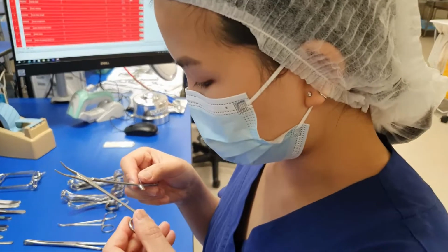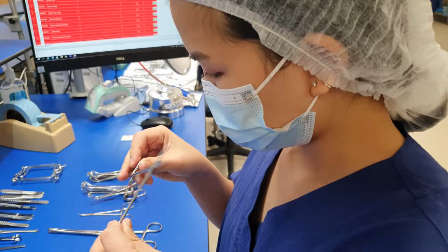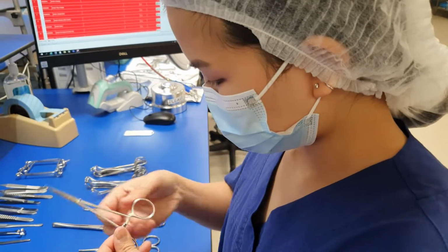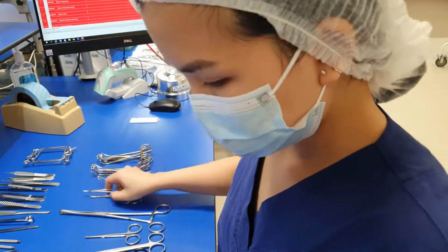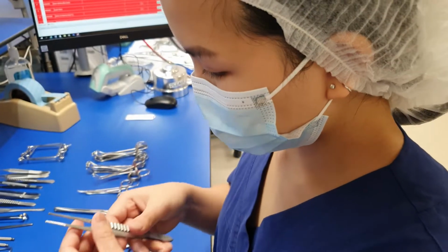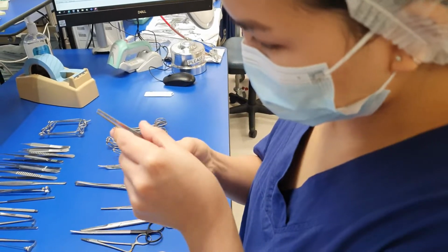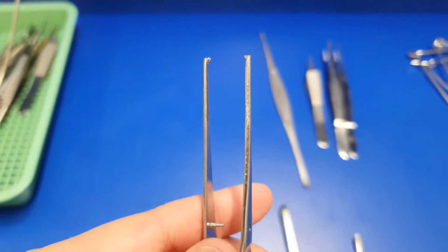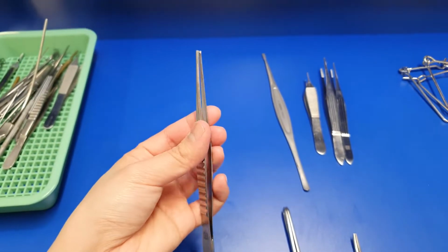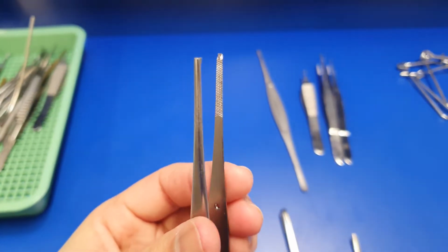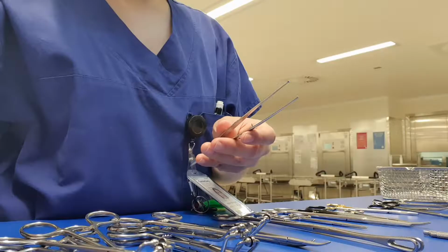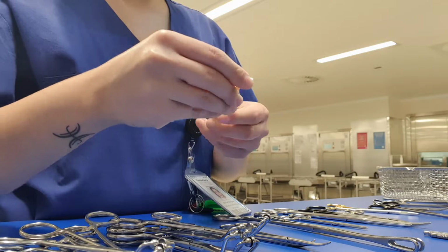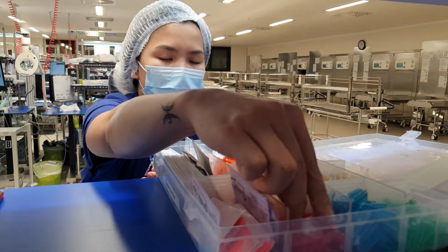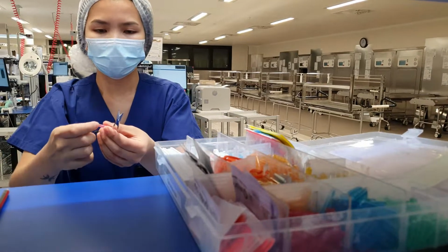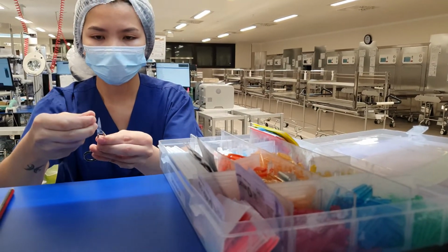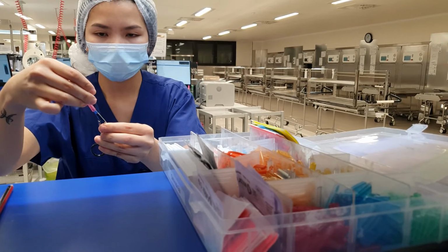In terms of instrument functionality, we check if tips align, scissors can cut correctly, if any instruments with insulation are intact, and lenses are clear with no blurring or distortion. It is important to know your devices and their functionality so you know what you are looking for, which are the critical areas. This also helps make inspection an efficient and quick process. Sharp instruments need tip protectors as these devices are delicate. This will prevent damage during handling and transport. This would also help protect and ensure the safety of the end user.